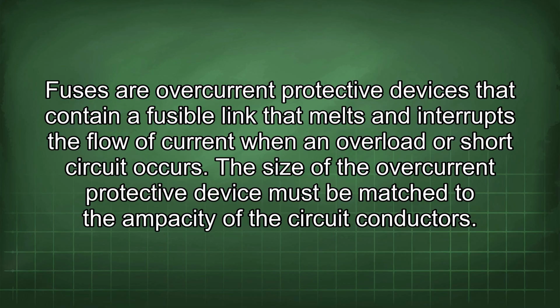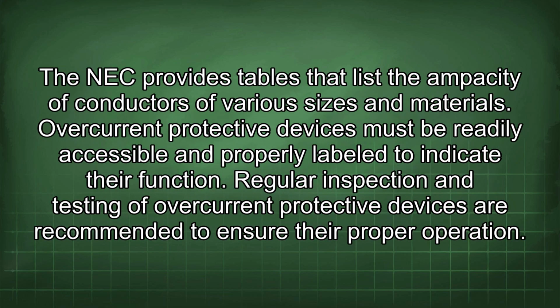The size of the overcurrent protective device must be matched to the ampacity of the circuit conductors. The NEC provides tables that list the ampacity of conductors of various sizes and materials. Overcurrent protective devices must be readily accessible and properly labeled to indicate their function. Regular inspection and testing of overcurrent protective devices are recommended to ensure their proper operation.